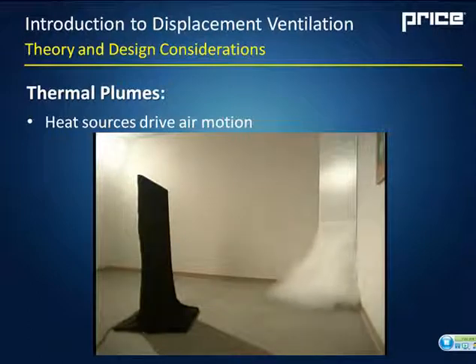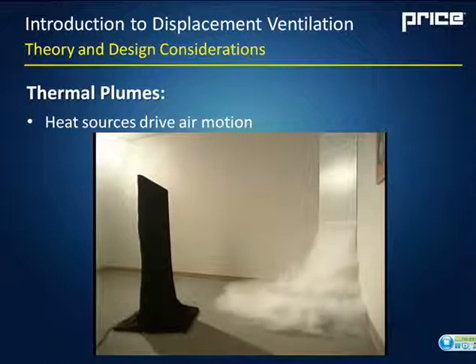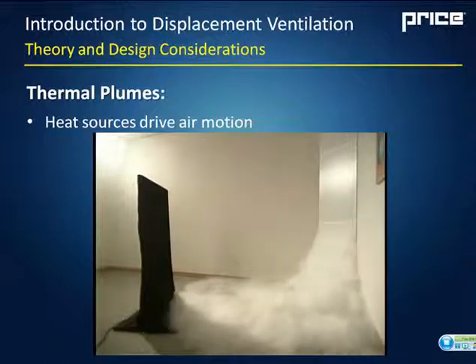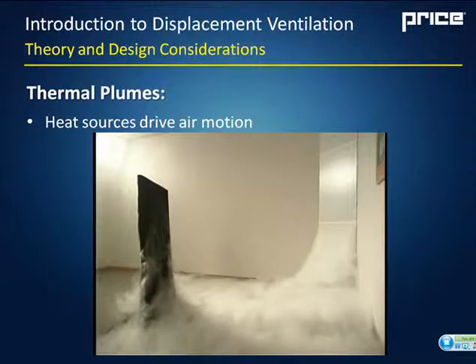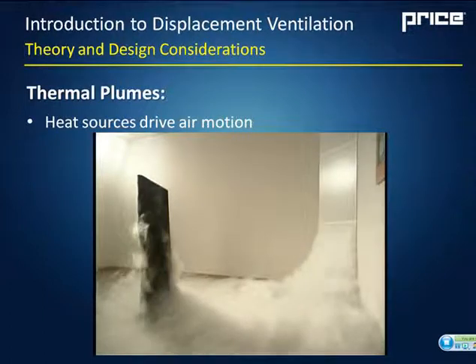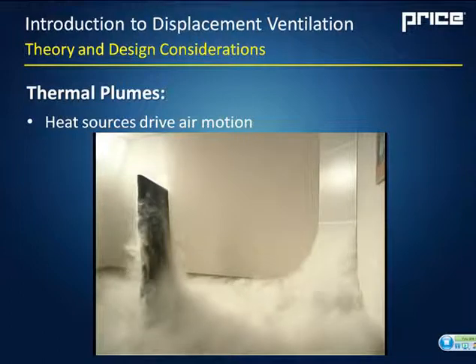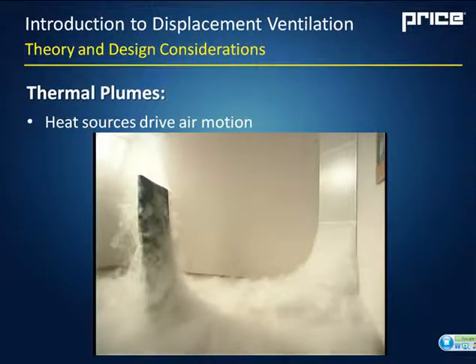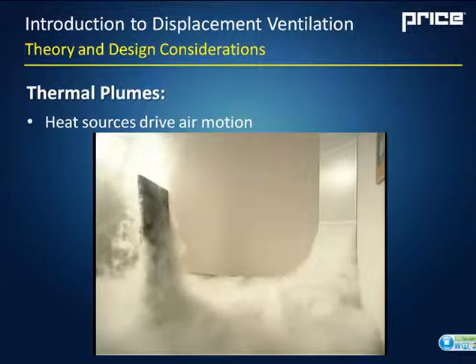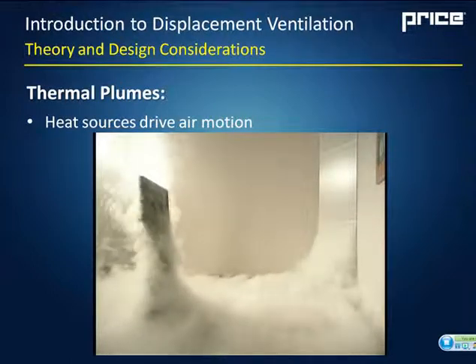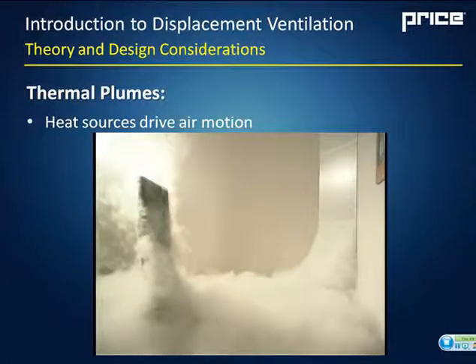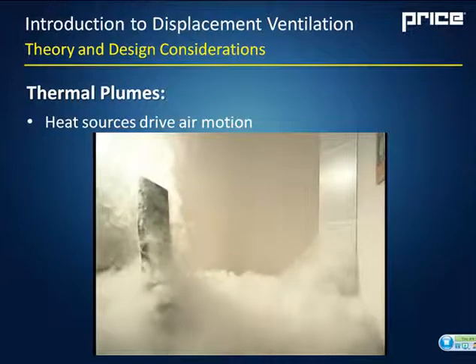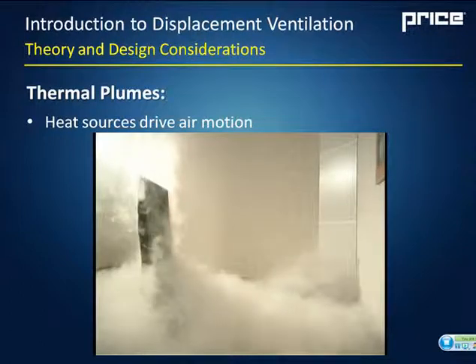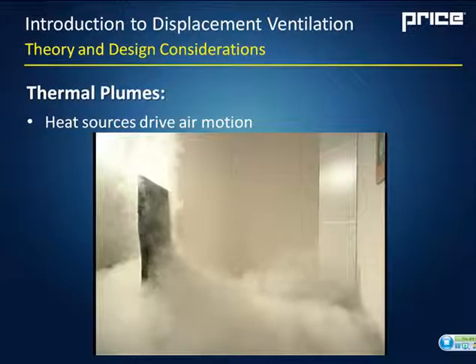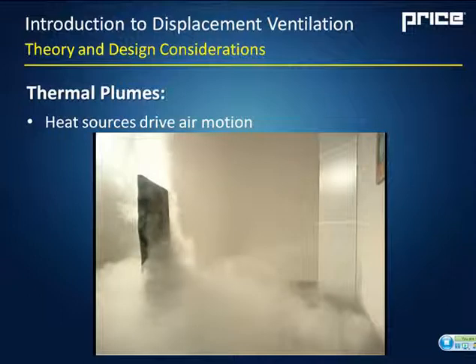So what this video is showing is that heat sources are basically going to drive the air motion in the room. Now the diffuser in the corner is basically spilling air out. It's going to travel across the floor, and this panel is depicting a warm body or a person in the room. So you can see how the cool air is moving up across the body. It's cooling the person or the piece of equipment or whatever this may be. And it's also delivering fresh, clean air right to the breathing zone. And you notice that smoke isn't being mixed back down, and it's not being mixed around the room. It's basically stratifying at the top of the room, and it's being pulled out by the returns.